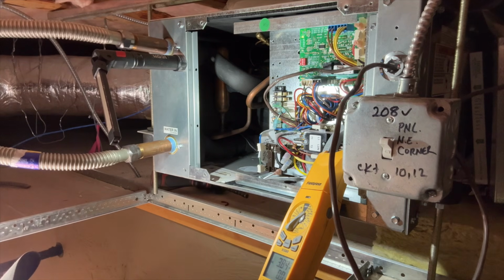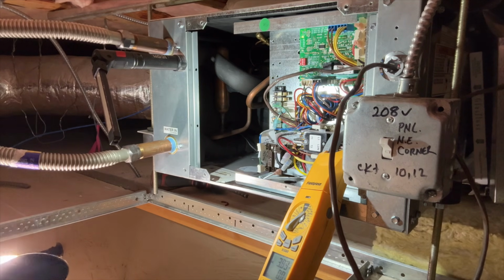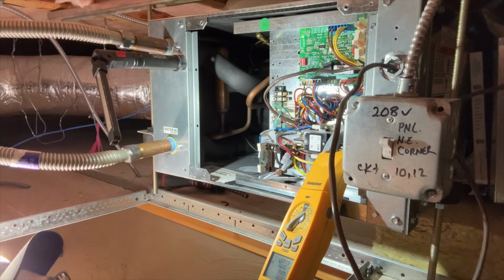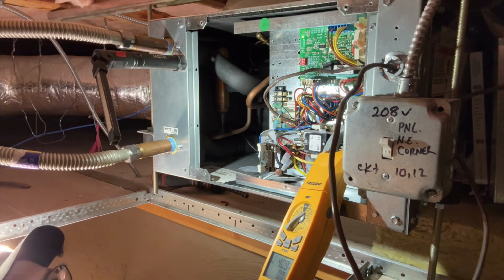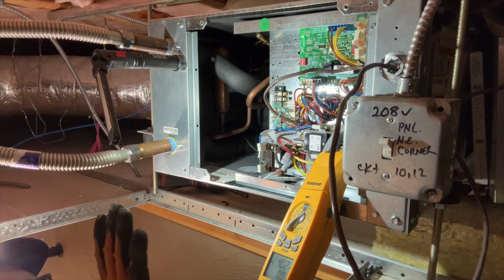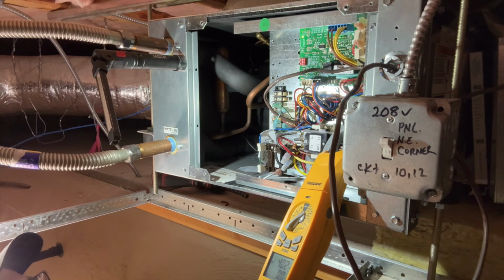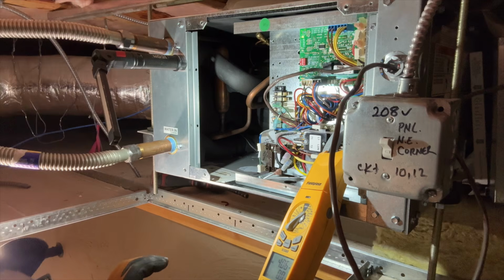Good. Yeah, we found our issue. It was a pinched wire that when it would vibrate just enough, it would touch the casing and cause a short to ground, which would trip the breaker. When I was pulling on the wires, I did an exaggerated version of what was happening, and we did get an arc, but thankfully everything seems to be functional. So we'll go ahead and close her up. All right, so that one was fun. Yeah, so that's our short right there.